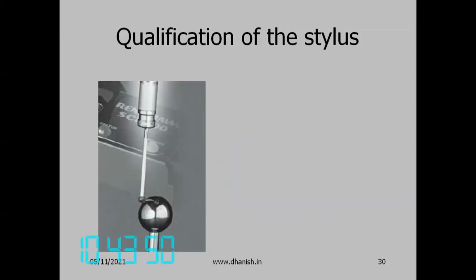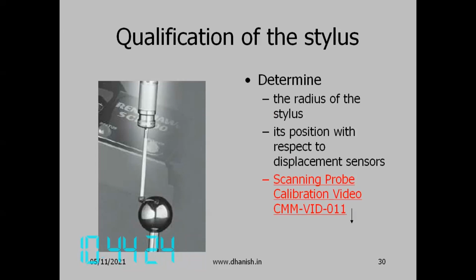Now the stylus qualification. We make the stylus contact the calibration sphere at a number of points. We know the diameter of the sphere, so based on that, we can calculate the diameter of the stylus and its position with respect to the displacement transducers. So where is it located now? So that next time, the stylus diameter or center can be taken to different positions. So the radius of the stylus is determined, and its position with respect to the displacement sensors.